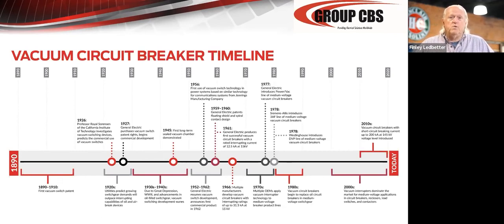A very small portion of it is still oil and gas, I would say 3 or 4%. That's primarily in explosive atmospheres and in places in the Southeast in the textile industry where they're still using a lot of oil breakers, refineries and explosive atmospheres, that sort of thing. But basically the oil breaker was a problem because of the oils and the organic insulation. Typically the insulation was wood or micarta, so it didn't survive very well.